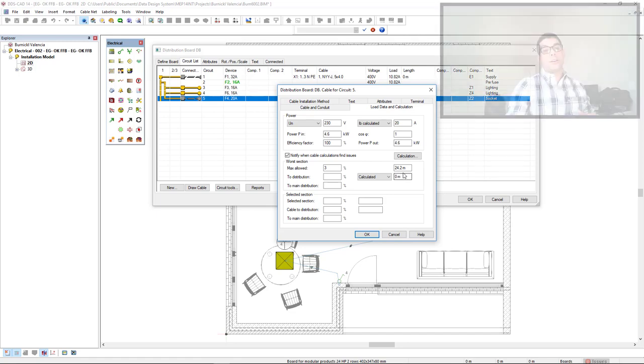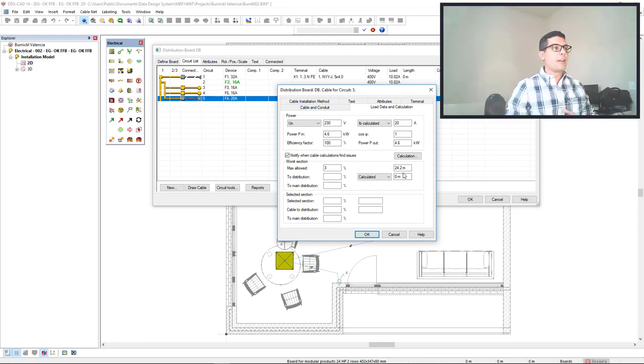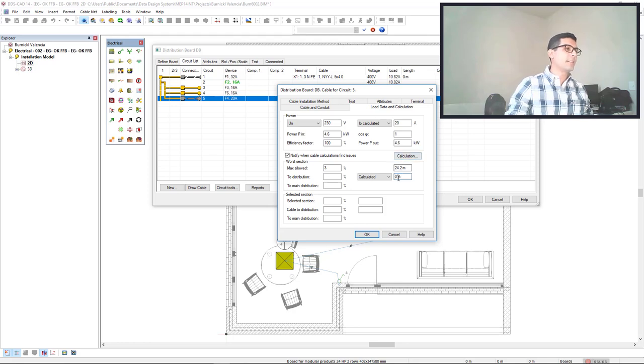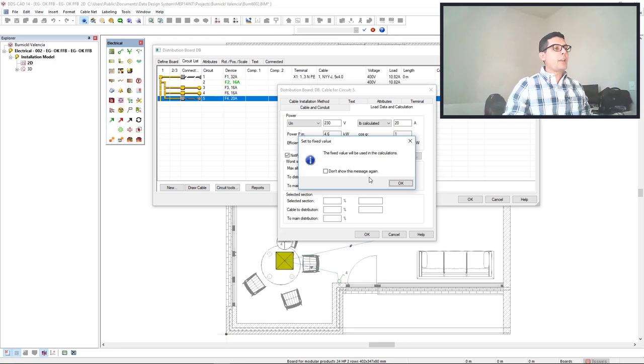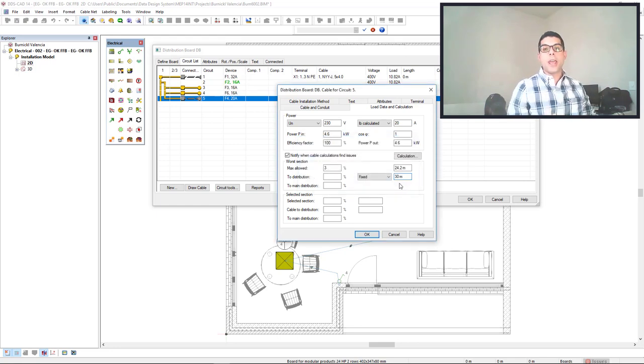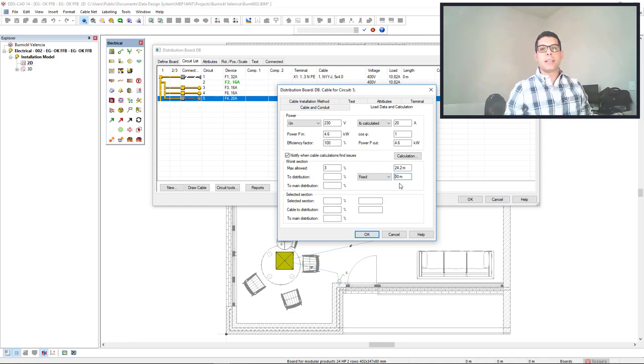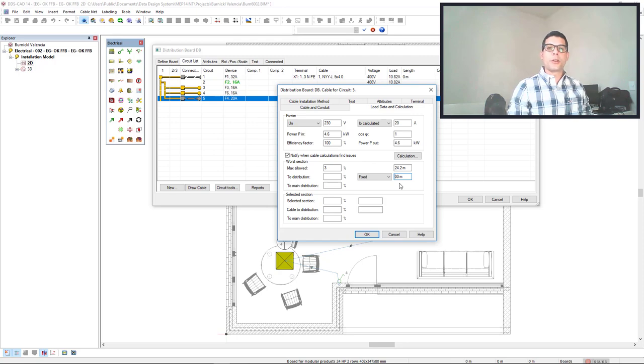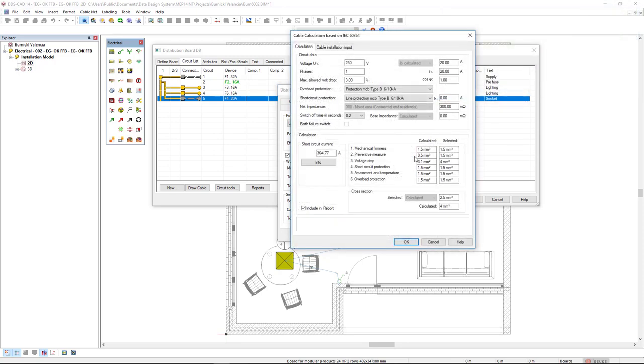If I know that this cable should go over this length, for instance, 30 meters, I could manually insert this value here, and I don't have to draw the cable in the model to calculate it. So, in this case, I'm inserting a length over the limit for the voltage loss. If we go to the button Calculation, DDSCAD is already calculating the cable for 4 square millimeters instead of the 2.5 square millimeters selected due to the voltage drop.